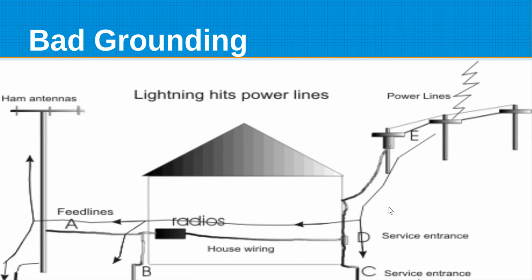This is a chart showing a typical setup where your power lines come in and go to your service entrance. There the power company will have put in a ground rod and connected it. It's usually not a very big wire. It's definitely not a number 6, because it's a safety ground, so you're not talking about much current. It's certainly not for lightning protection.